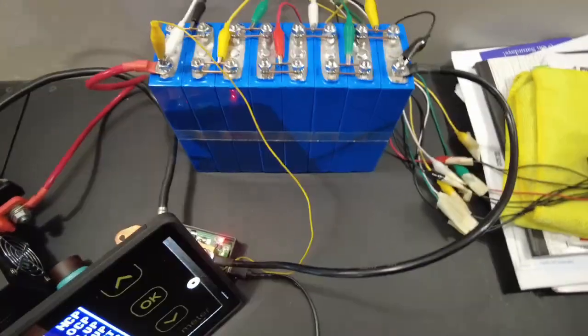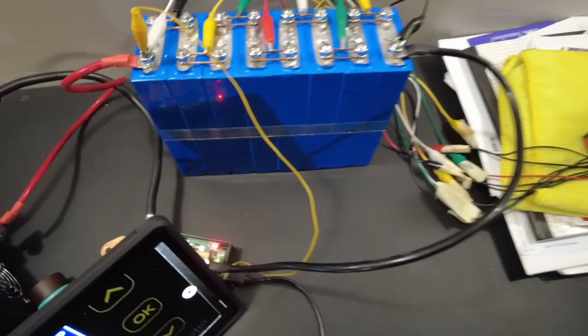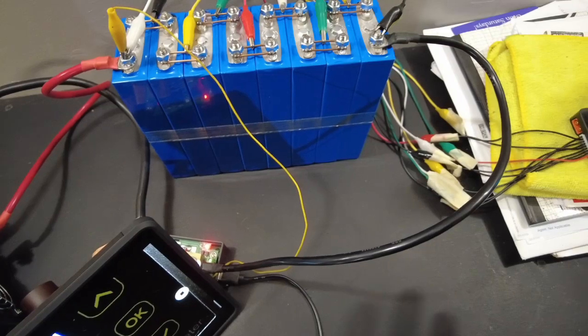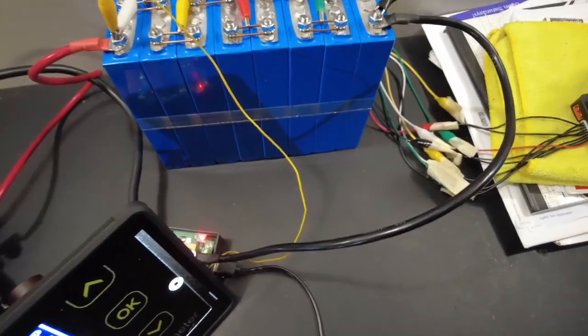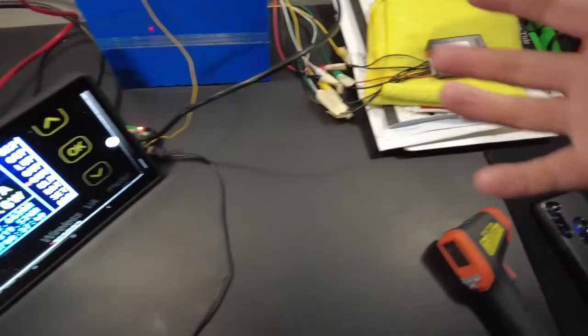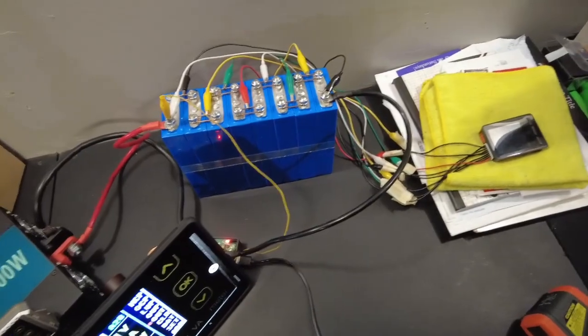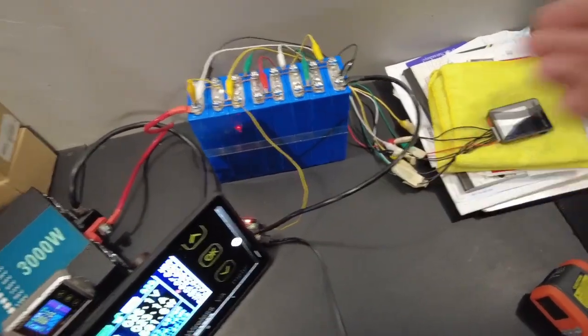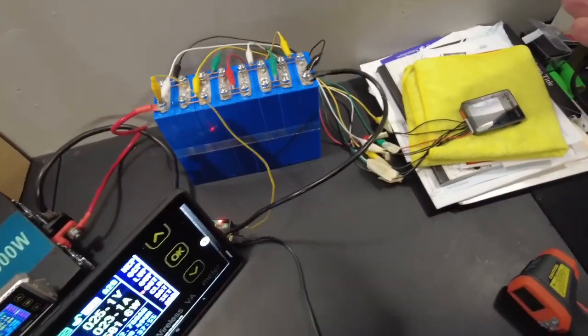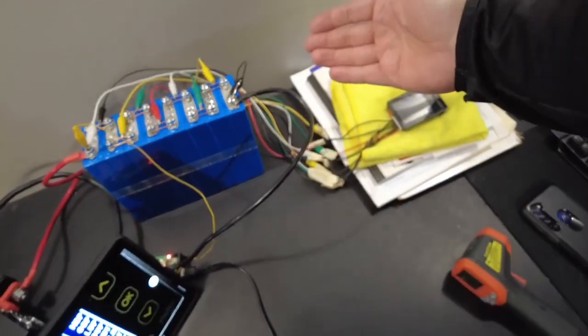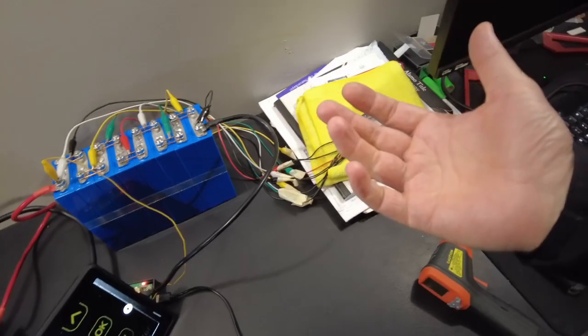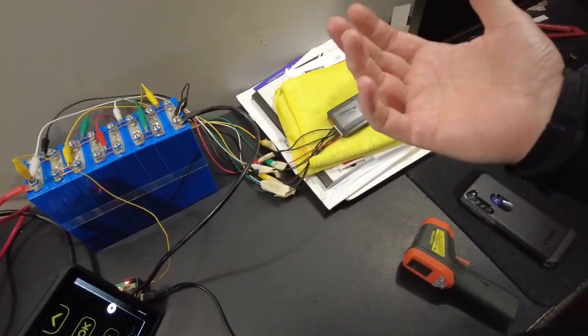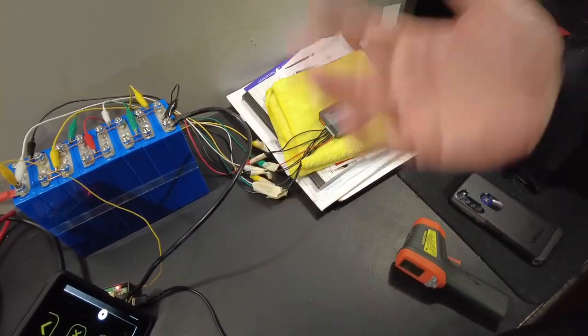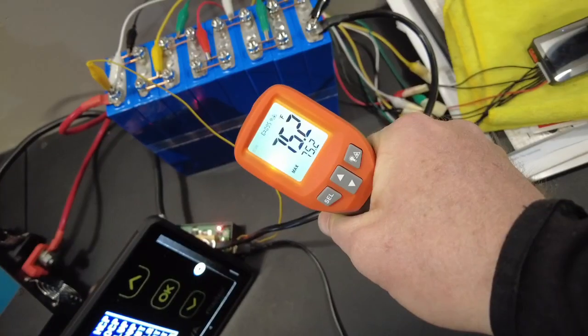30 amps, be it DC, AC, pretty much no difference. The only difference that you have to deal with when it comes to DC voltage versus AC voltage is DC voltage has more of a drop with the distance of the wire that you have. So you have to take that into consideration. But there's plenty of calculators online. Just basic Ohm's law stuff.